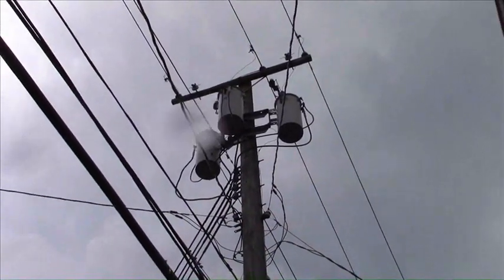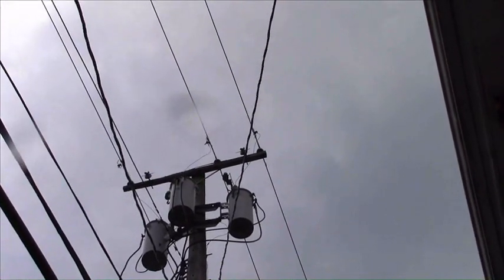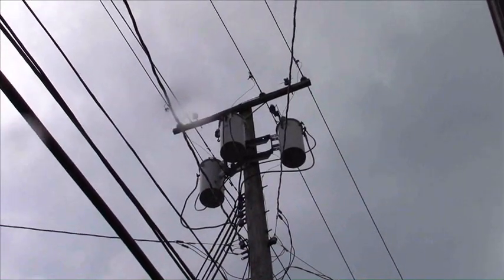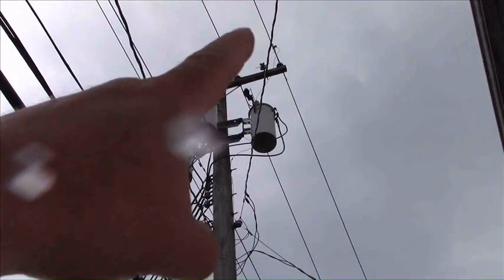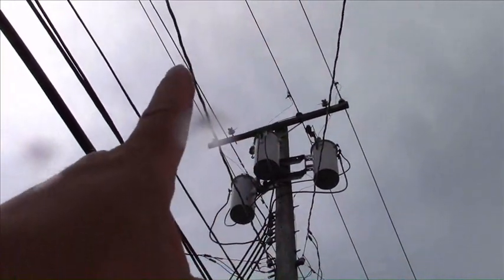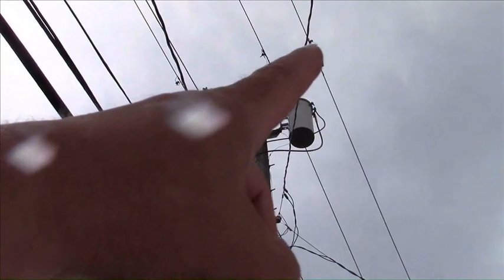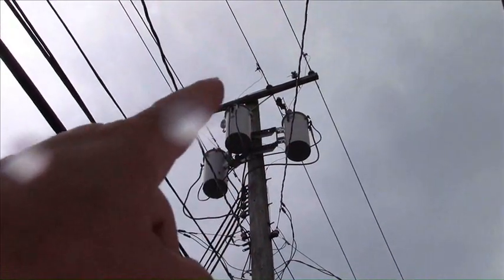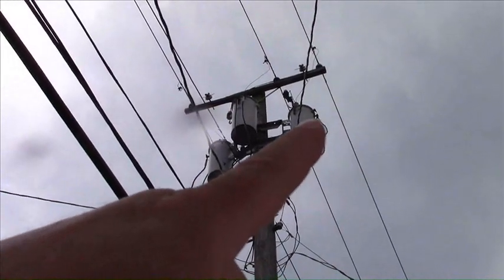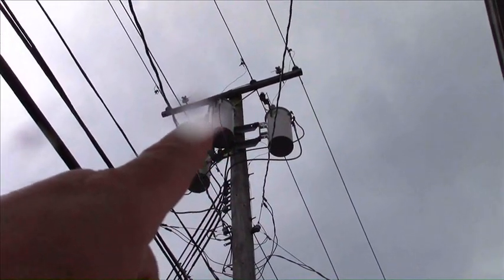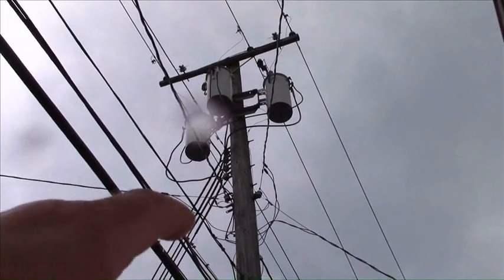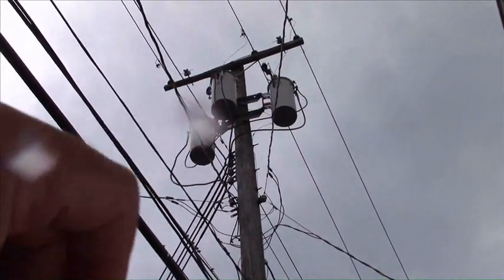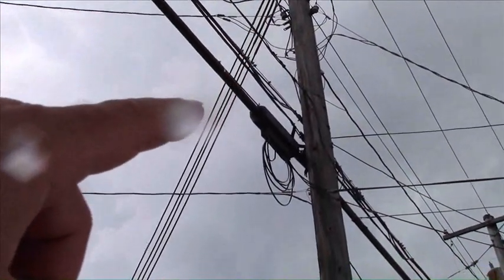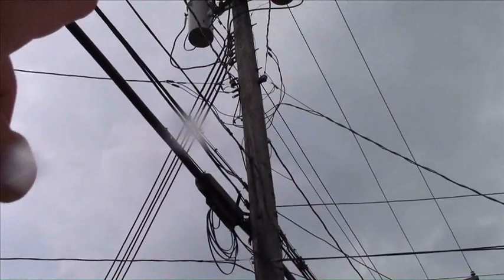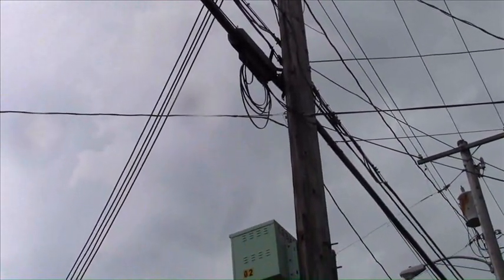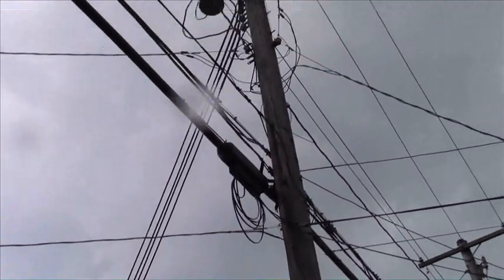Okay, this is an example of the 480 volt 3-phase configuration that a lot of businesses and industries have. Way up at the top you have the 3 high voltage phase wires going, and from each phase wire you have one thin little wire coming down to each of the 3 transformers. And then on each of the 3 transformers, the center cable is the neutral, and they are all tied together. So you have one neutral line and 3 phase lines. That makes up the 4 cables going down to this building. The top wire of the 4 is the neutral, and you have 3 phases below that, each at 480 volts.